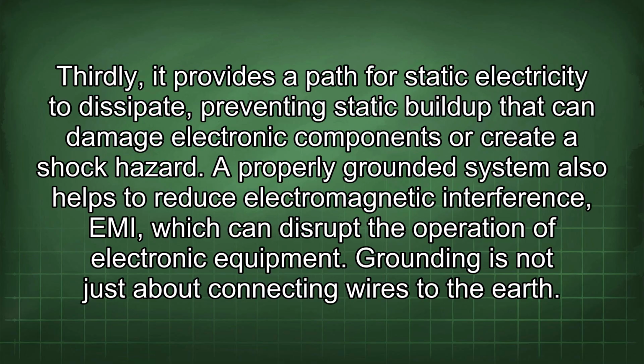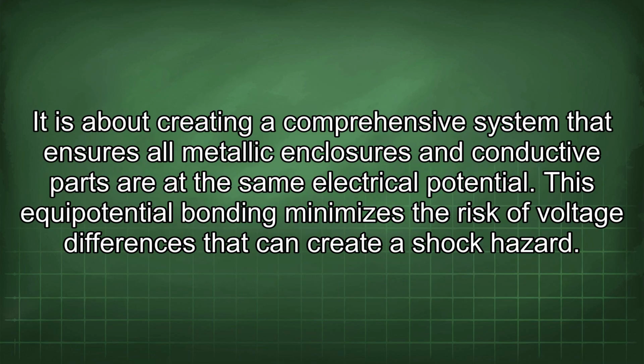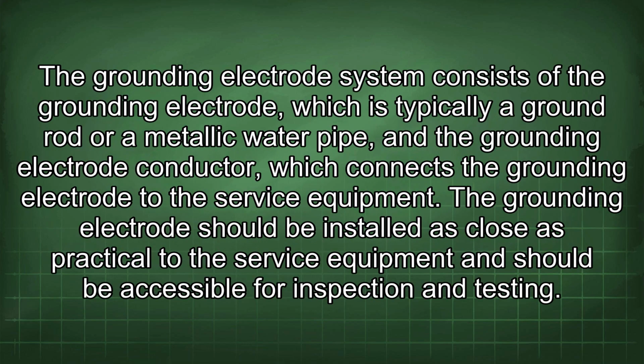electronic equipment. Grounding is not just about connecting wires to the earth. It is about creating a comprehensive system that ensures all metallic enclosures and conductive parts are at the same electrical potential. This equipotential bonding minimizes the risk of voltage differences that can create a shock hazard. The grounding electrode system consists of the grounding electrode, which is typically a ground rod or a metallic water pipe, and the grounding electrode conductor, which connects the grounding electrode to the service equipment.